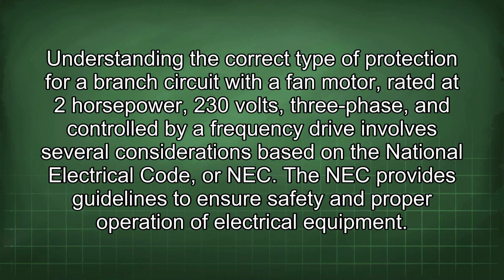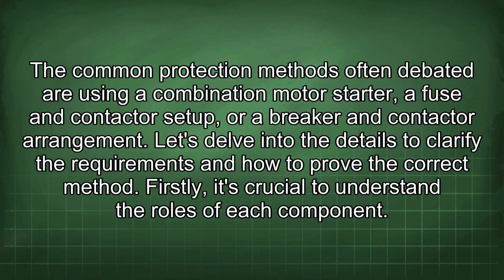Understanding the correct type of protection for a branch circuit with a fan motor, rated at 2 horsepower, 230 volts, 3-phase, and controlled by a frequency drive involves several considerations based on the National Electrical Code, or NEC. The NEC provides guidelines to ensure safety and proper operation of electrical equipment. The common protection methods often debated are using a combination motor starter, a fuse and contactor setup, or a breaker and contactor arrangement. Let's delve into the details to clarify the requirements and how to prove the correct method.